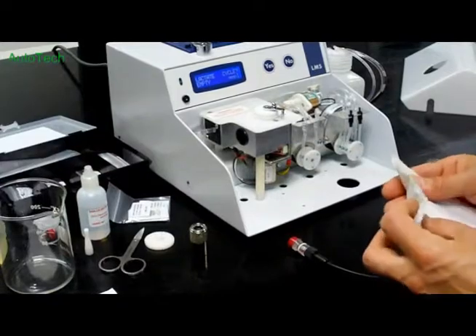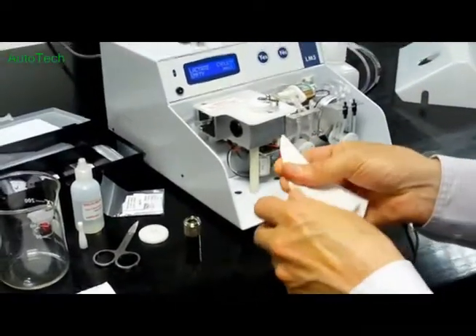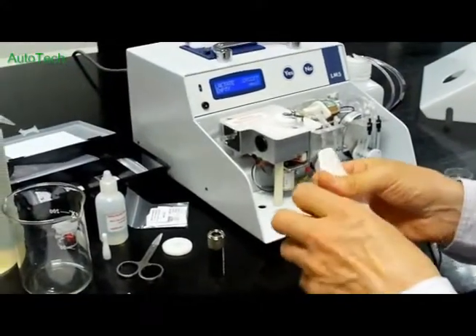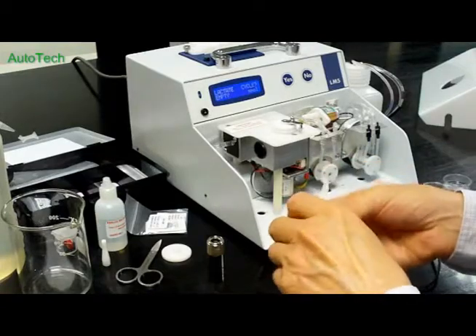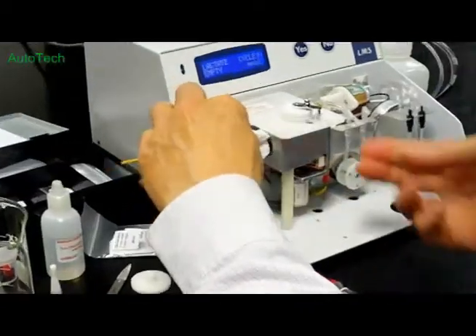So before reinserting the electrode, we need to make sure the electrode aperture is dry. So using a tissue, just dry up inside the electrode aperture, just to make sure there's no moisture at all.